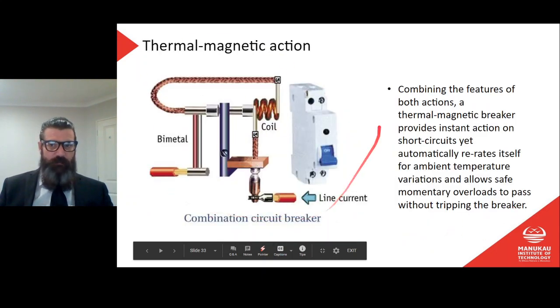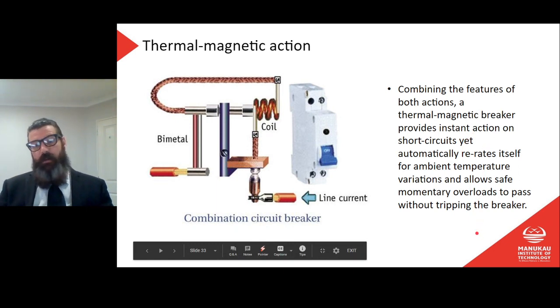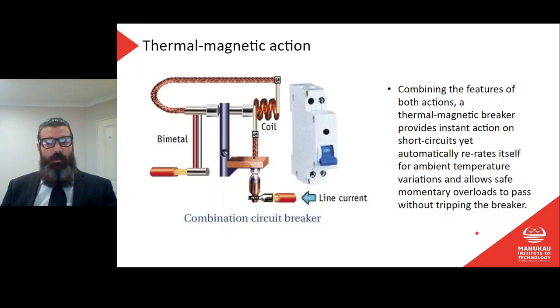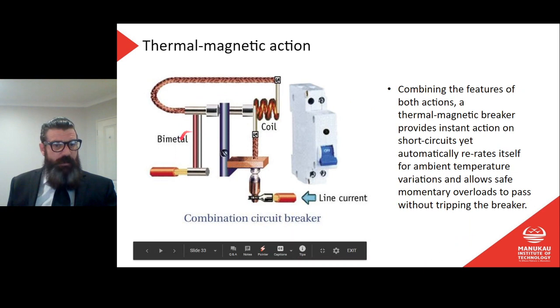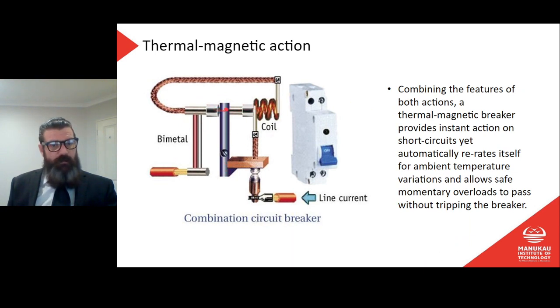And here we have the combination of the thermal and magnetic action. Combining the features of both actions, a thermal magnetic breaker provides instant action on short circuits, yet automatically re-rates itself for ambient temperature variations and allows safe momentary overloads to pass without tripping the breaker. Yeah, so here we have it here. Here is our bimetal, here is our latching mechanism, here is our coil. So those two devices are operating on opposite sides of the latching mechanism, but either way, once they cause the latching mechanism to move, then our contacts will open.